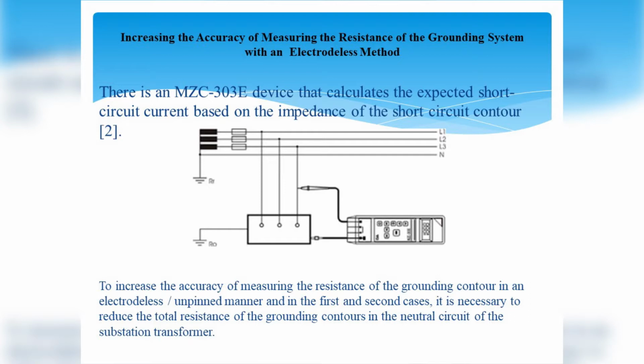Based on the meter reading and measuring the expected short circuit current, it is possible to select the required values of residual current circuit breakers for each power supply circuit. The device allows to monitor the integrity of the zero protective conductors, to carry out measurements without disconnecting the power supplies and protection, and to evaluate the resistance of the grounding device. When assessing the resistance of the grounding device, instead of the resistance of the neutral wire, the resistance of the investigated circuit in the grounding contour of the substation feeder transformer will be included in the measurement result.